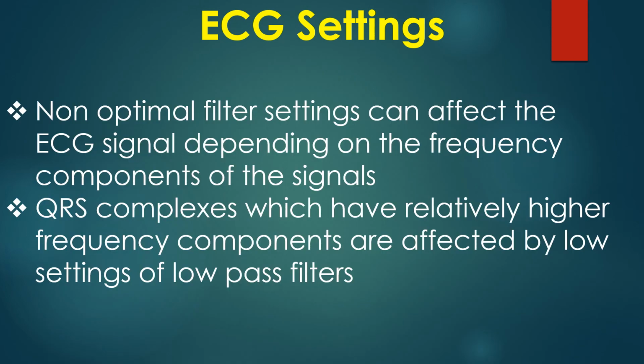Non-optimal filter settings can affect the ECG signal depending on the frequency of components. QRS complexes which have relatively higher frequency components are affected by low settings of low pass filters.